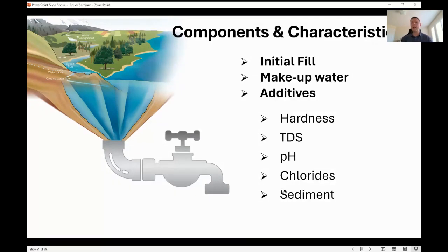And some of the main additives you're looking at with a hydronic system, I find, is hardness, which generally consists of calcium, magnesium. But there's also total dissolved solids. That's everything that's dissolved in there within a certain size range. Your pH is important. Chlorides as well, especially with a stainless steel product, because chlorine is the one thing that really kills stainless steel, whether it's in the water or actually also in the air.